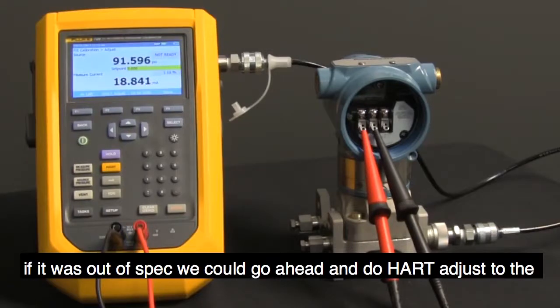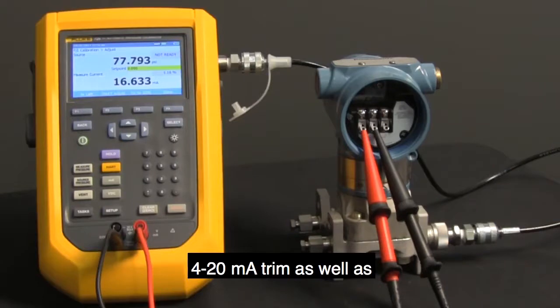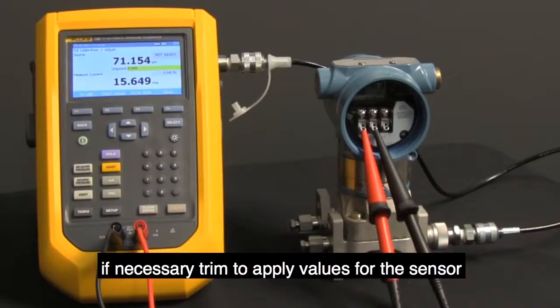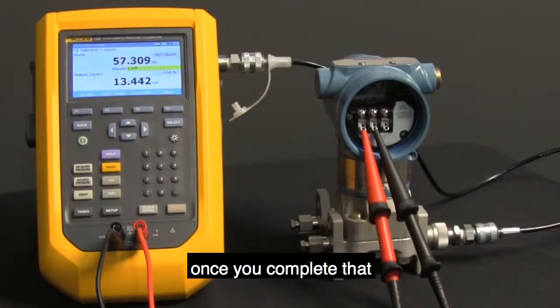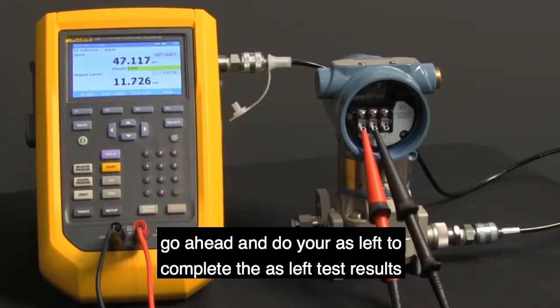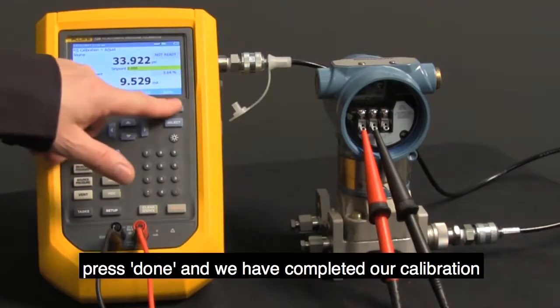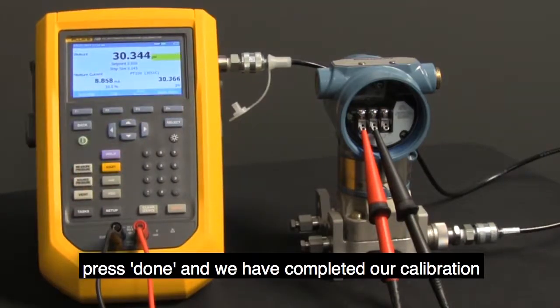If it was out of spec, we could go ahead and do HART adjust to the 4-20 milliamp trim as well as, if necessary, trim to applied values for the sensor. Once you complete that, go ahead and do your as-left to complete the as-found and as-left test results. Press done and we have completed our calibration.